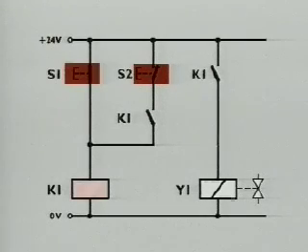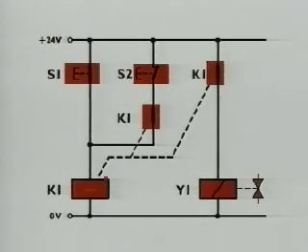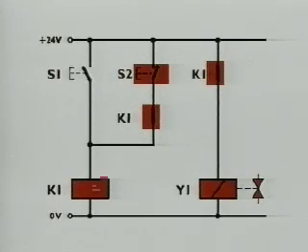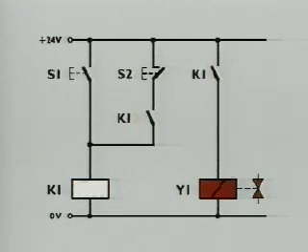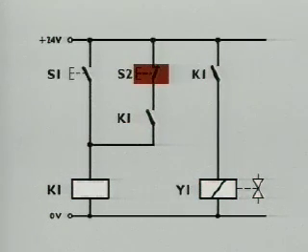When push button S1 is pressed, relay K1 picks up and the two contacts K1 close. One keeps the relay coil energized and the other switches current to the solenoid valve. This means that the relay remains in this position, even if contact S1 is opened, until S2 is opened. If S1 and S2 are actuated simultaneously, the relay coil remains energized. This is called a dominant on latch.